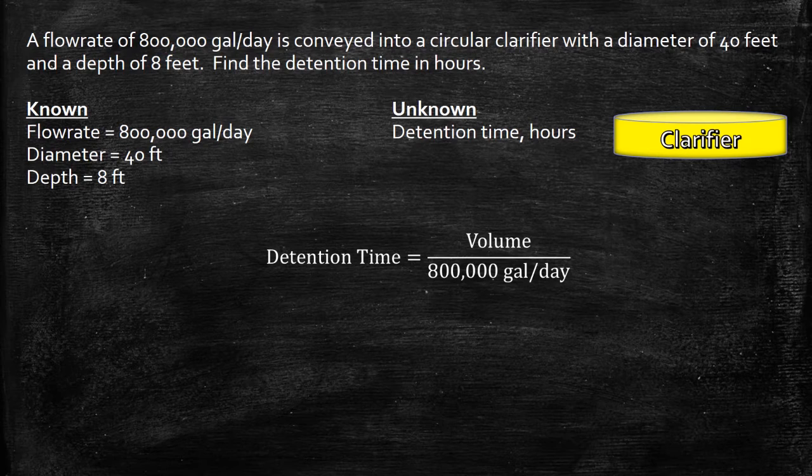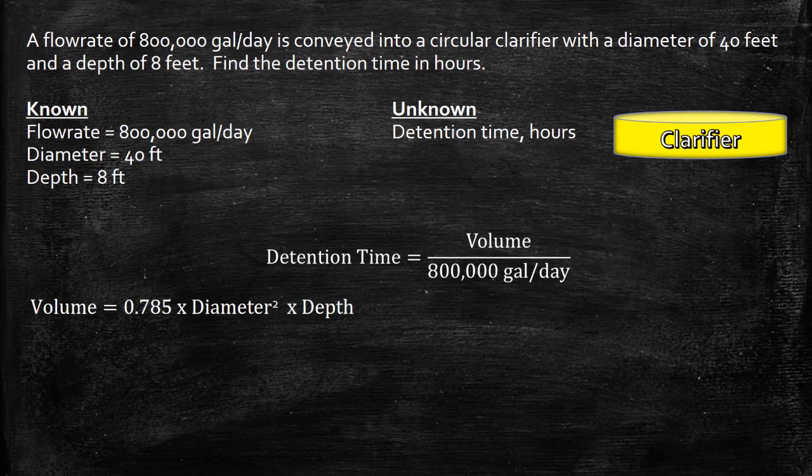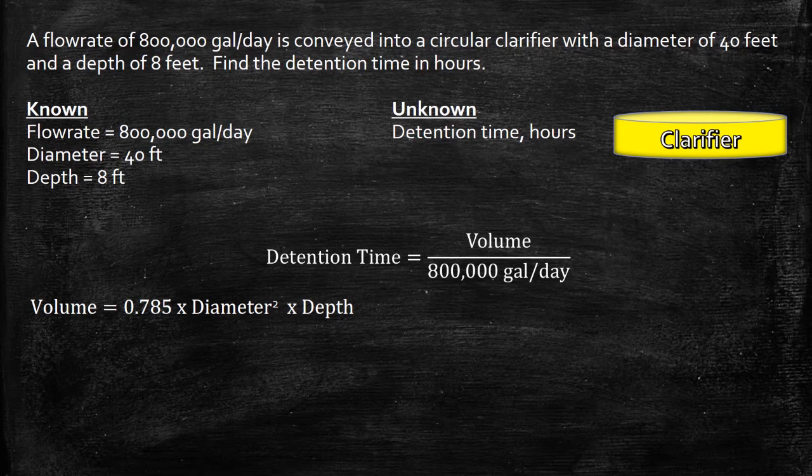The volume of this clarifier is just the volume of a cylinder. So let's write down that formula, 0.785 multiplied by diameter squared multiplied by depth. Do we have diameter and depth? If you look under the knowns, we're given the diameter is 40 feet and the depth is 8 feet. Let's plug them in.